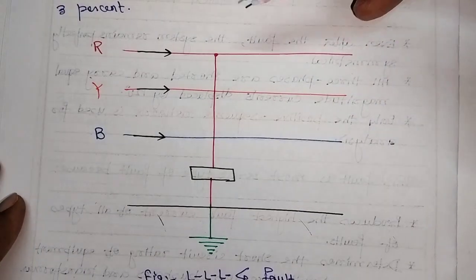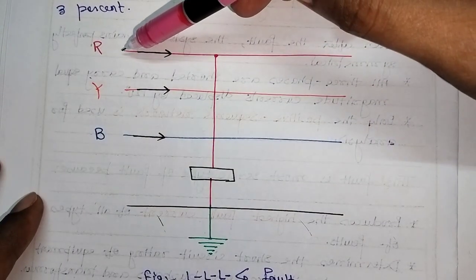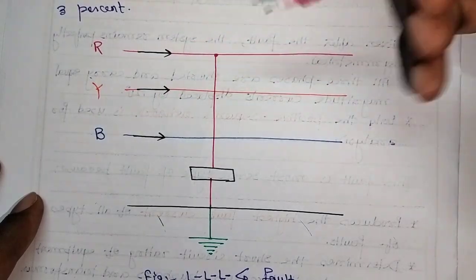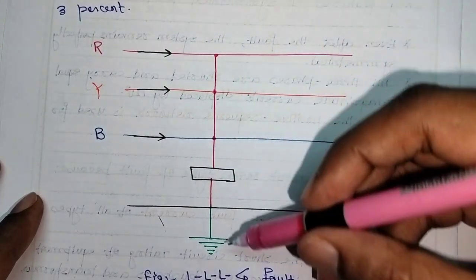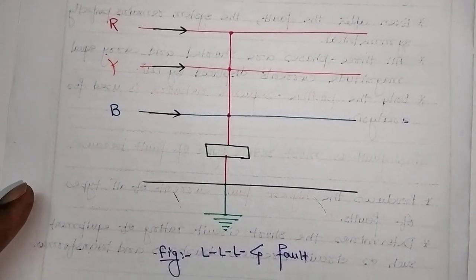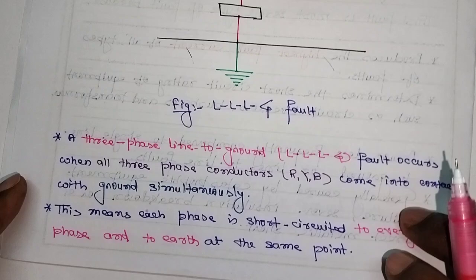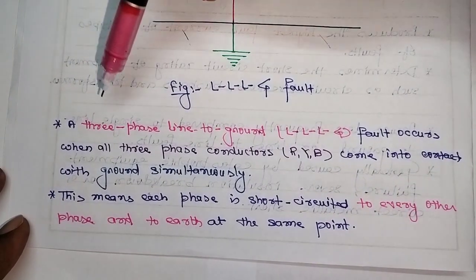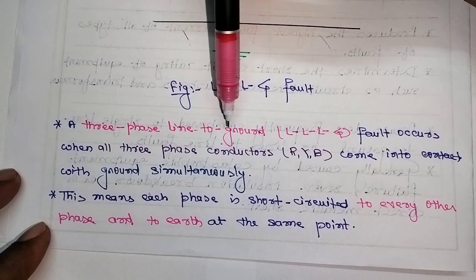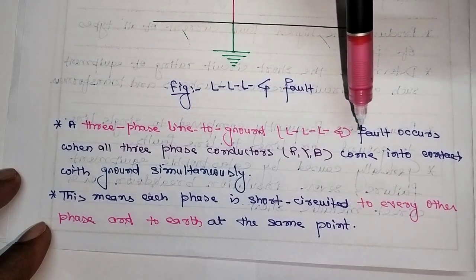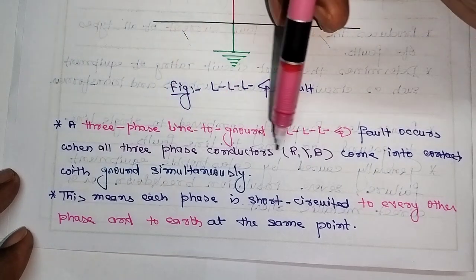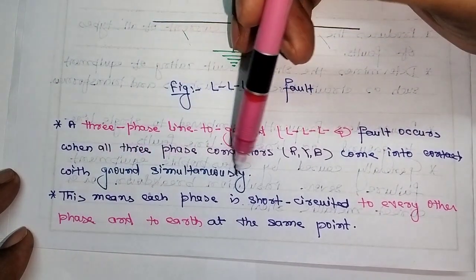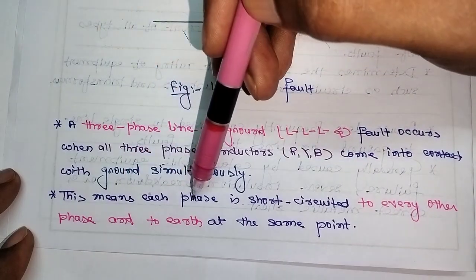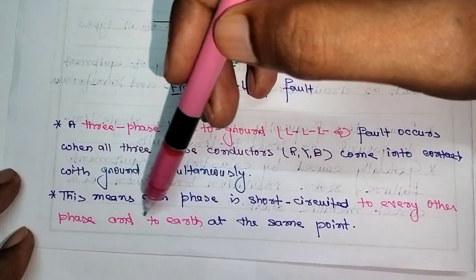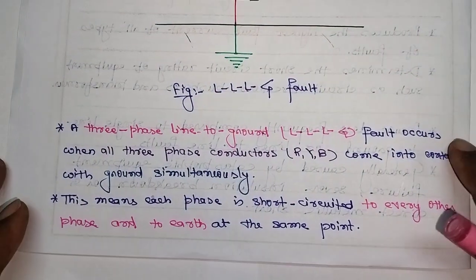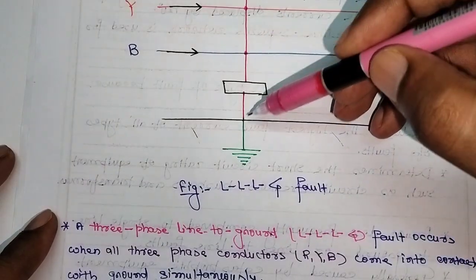In the diagram we can see here we have the three conductors R, Y and B. When they are shorted and grounded also, such a type of fault is called the line to line ground fault. Next we have the three-phase line to ground fault, that is the L3G fault, which occurs when all three phase conductors R, Y, B come into contact with the ground simultaneously. This means each phase is shorted to every other phase and to the earth at the same point. Also we have shown here that it is getting shorted at the same point only.